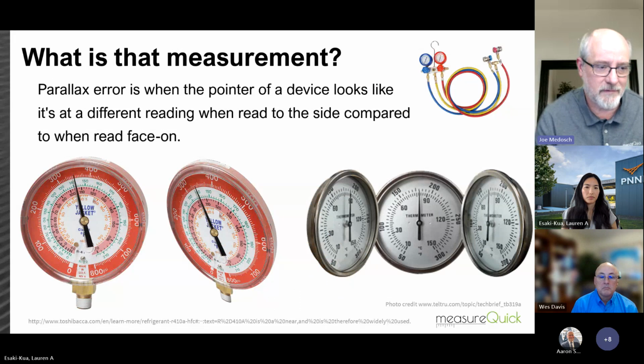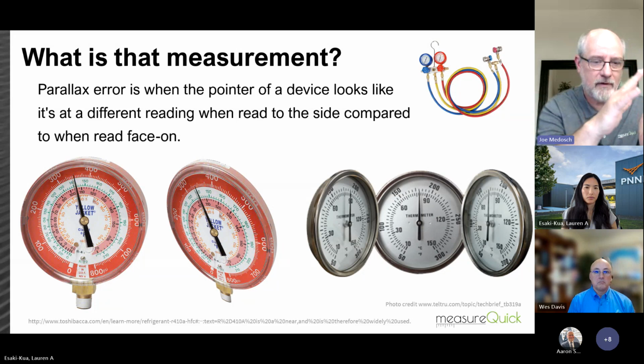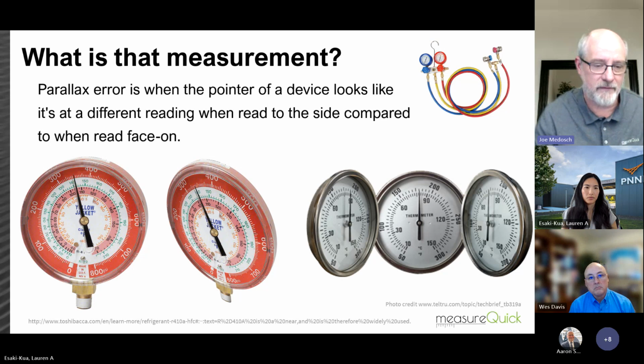So what is that measurement? There's something called a parallax error—if you're looking at something with a needle, depending on how far away the needle is from what you're reading, it could give you an entirely skewed version of what's happening. You can see on the right, with a temperature gauge, it's the same for a refrigerant gauge—if you're not looking at it straight on, with the shadow directly behind the needle, you may not be reading it exactly right.